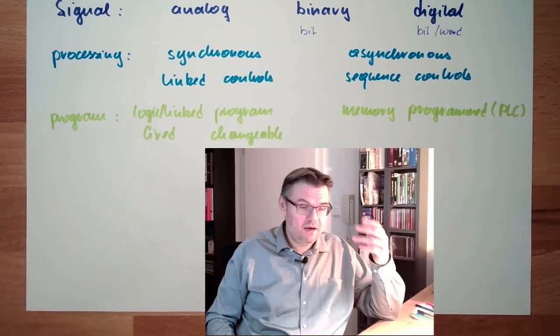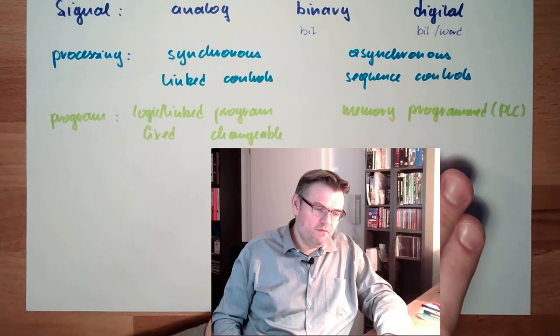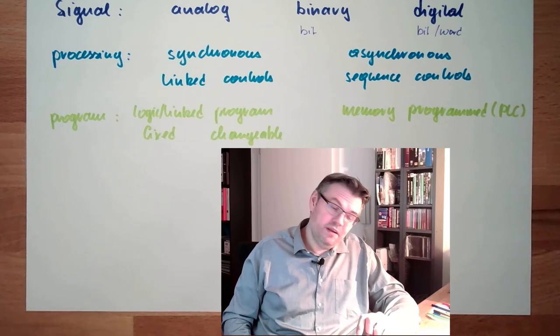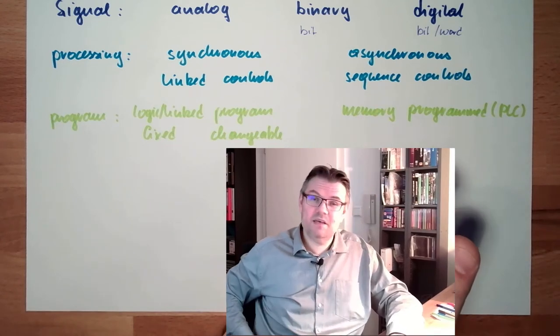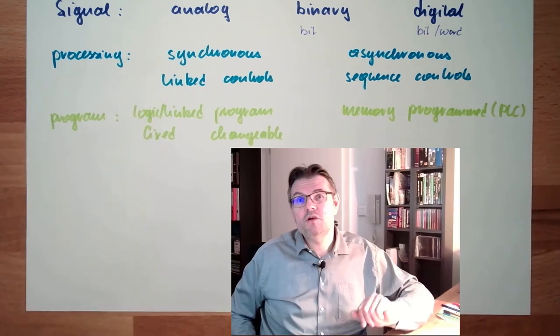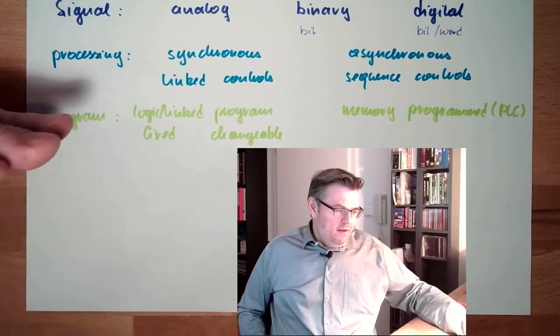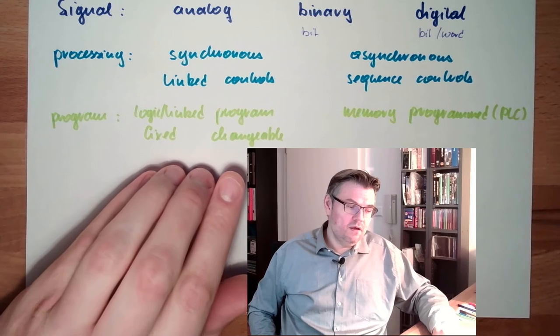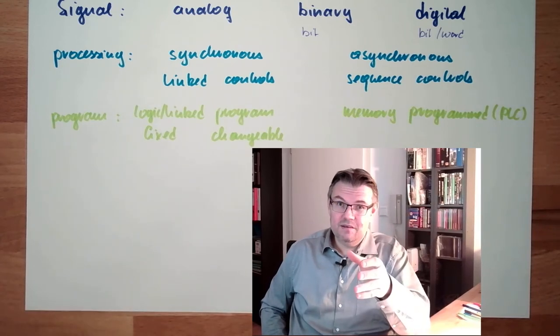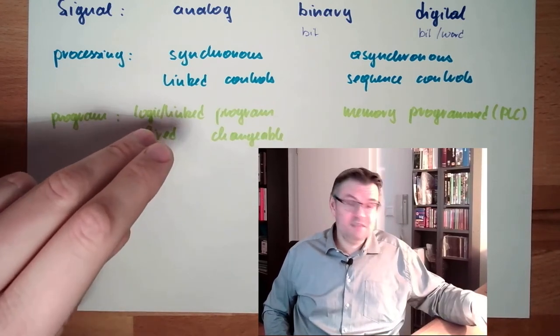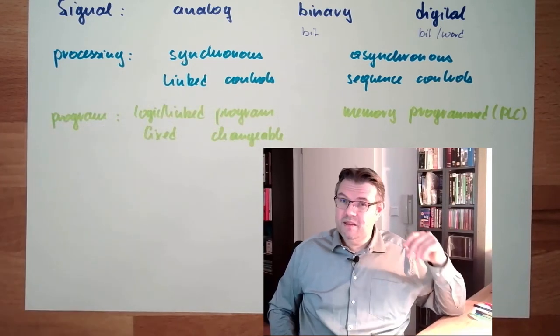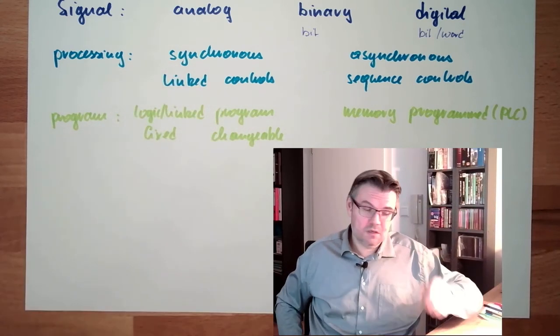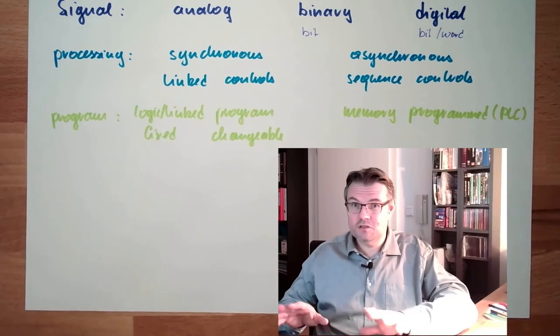You don't need programming devices. If it's really the case that there is hardwired and so on, you can even think about it and see the logic right in front of you. So you don't even need to know any programming languages. Here you do have this. You need to know programming languages. You need a computer, you need to program this. You need special information. And also, such PLCs are usually asynchronous. So those asynchronous types, they are not that fast. Here, in the PLC, I mean, 100 Hz is already pretty high. If it has to be faster, you really need to think about sub-programs and so on. Then it's getting sophisticated. Here, it's no issue. However, if you want to design such program, you really have to think about it before. If you then, during commissioning phase, you cannot change too much. That's difficult. Because if there is an error inside the program, then you might end up in a situation where it's not longer possible to adapt this program, even with tools. Here, no problem at all. Change the software, working.